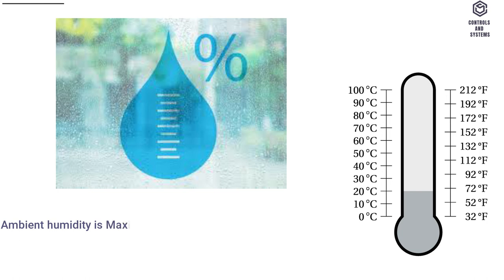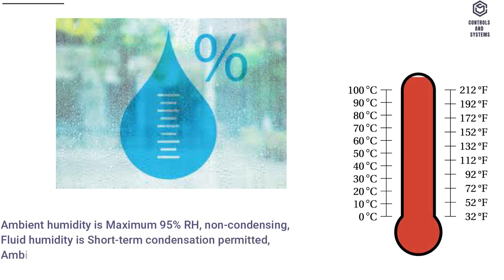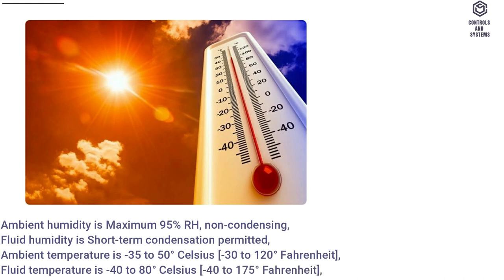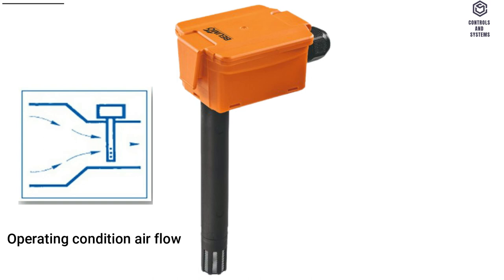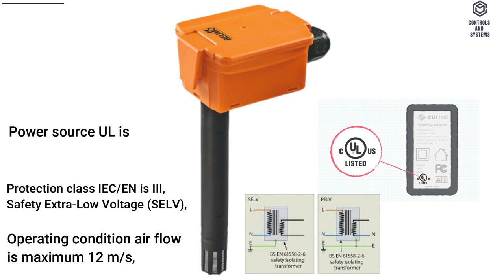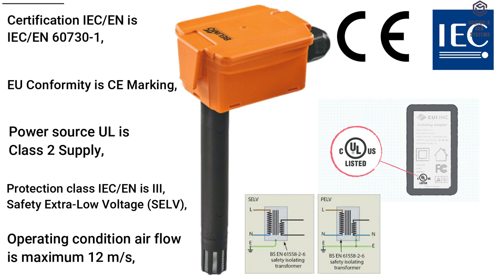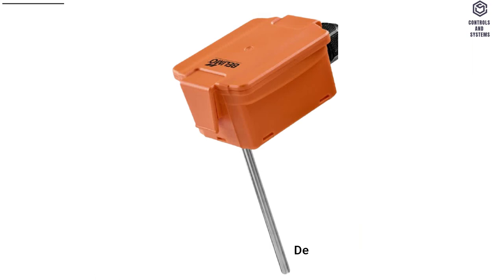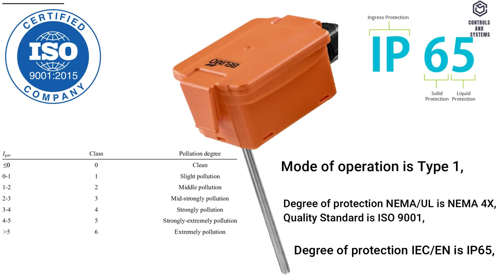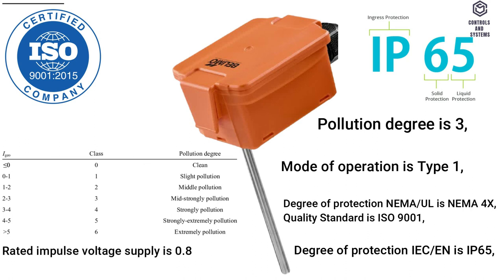Safety Data: Ambient humidity is maximum 95% RH non-condensing. Fluid humidity: short-term condensation permitted. Ambient temperature is −35 to 50°C (−30 to 120°F). Fluid temperature is −40 to 80°C. Operating condition air flow is maximum 12 m/s. Protection class IEC/EN III, safety extra-low voltage (SELV), power source class 2 supply. EU conformity marking. Certification IEC/EN 60730-1. Degree of protection IP65. Degree of protection NEMA UL is NEMA 4X. Quality standard is ISO 9001. Mode of operation is Type 1. Pollution degree is 3. Rated impulse voltage supply is 0.8 kV. Construction is independently mounted control.